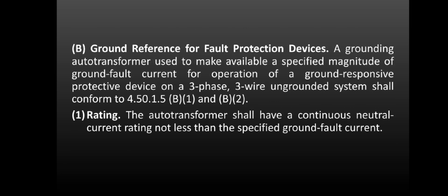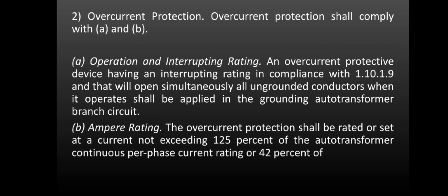Ground reference for fault protection devices. A grounding autotransformer used to make available a specified magnitude of ground fault current for operation of a ground-responsive protective device of a three-phase, three-wire ungrounded system shall conform to 4.50.1.5. 1. Rating. The autotransformer shall have a continuous neutral current rating not less than the specified ground fault current. 2. Overcurrent protection. Overcurrent protection shall comply with A and B. A. Operation and interrupting rating. An overcurrent protective device having an interrupting rating in compliance with 1.10.1.9 and that will open simultaneously all ungrounded conductors when it operates shall be applied in the grounding autotransformer branch circuit. B. Ampere rating. The overcurrent protection shall be rated or set at a current not exceeding 125% of the autotransformer continuous per-phase current rating or 42%.